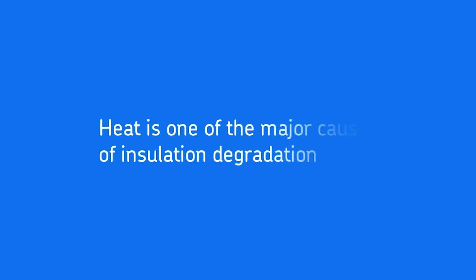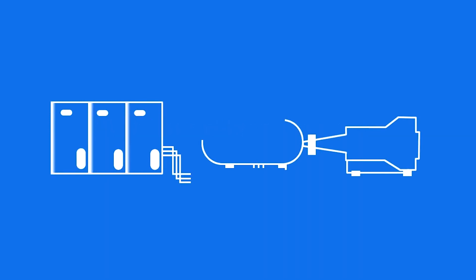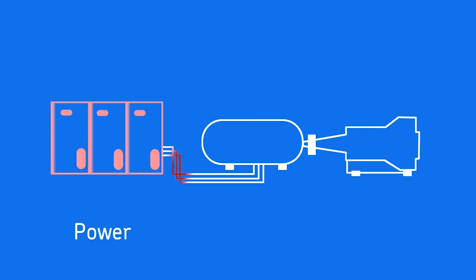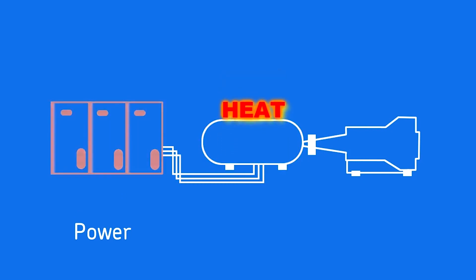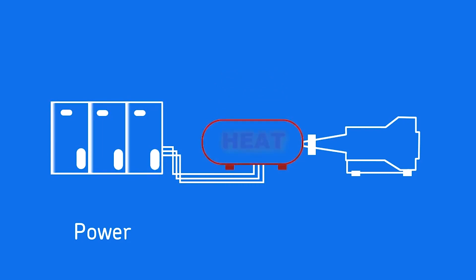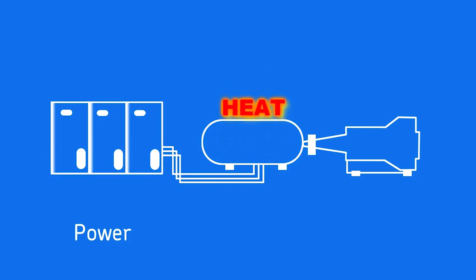One of the major causes of insulation degradation is heat. To understand more about what causes excess heat in the motor, let's look at the entire power, motor, and load system. Electric machines are designed for good incoming power conditions. When power conditions deteriorate, excessive currents can flow in the machine, generating excess heat and shortening machine life. Incoming power tests look at voltage and current levels, distortion, and balance.